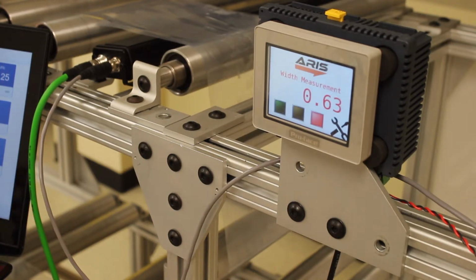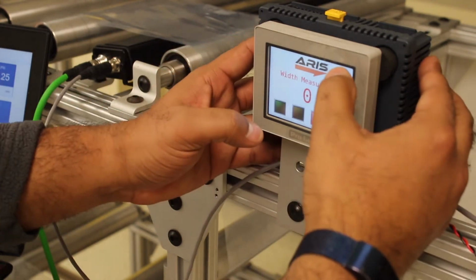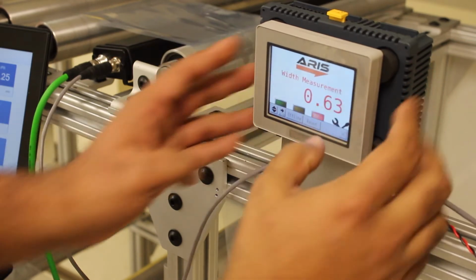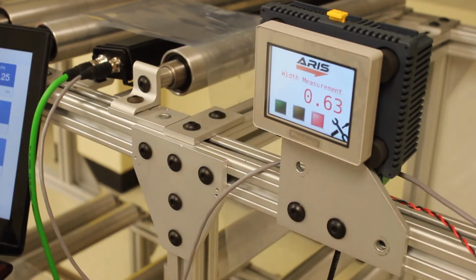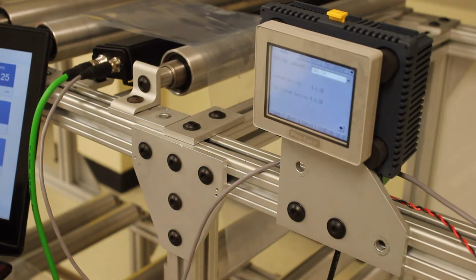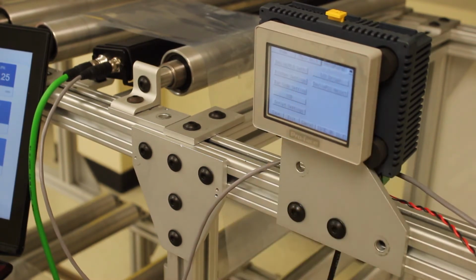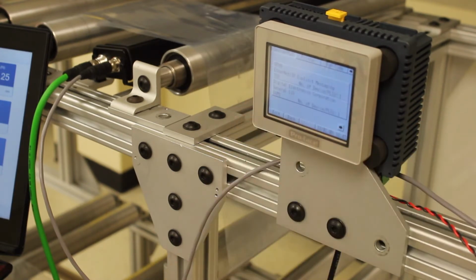One of the first things we want to do to get the PLC to communicate with the sensor is to tell the PLC what the IP address of the sensor is. In order to do that, we're going to press these corners one after the other and then go to offline. This shows the main screen here in the offline menu. We click on peripheral, and within the peripheral, we select device/PLC setting. And here we're going to use the Ethernet IP explicit messaging protocol.